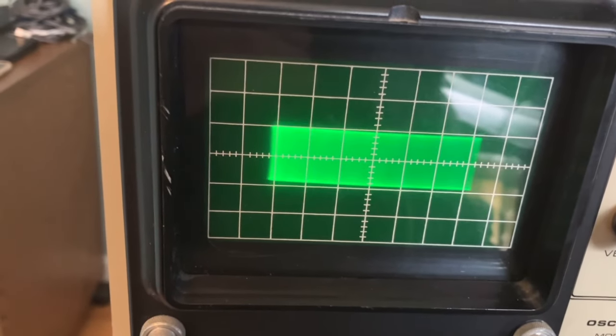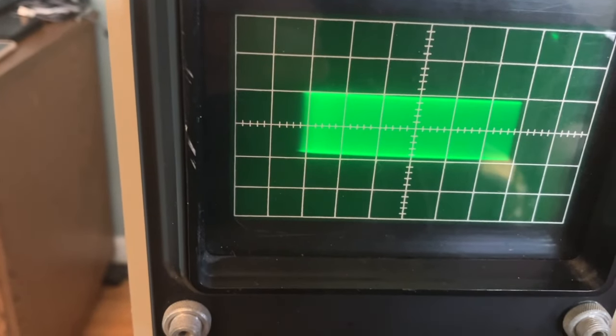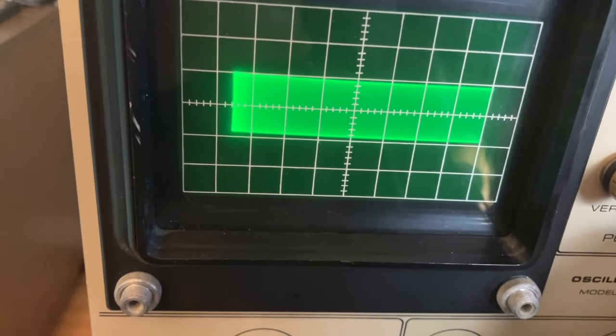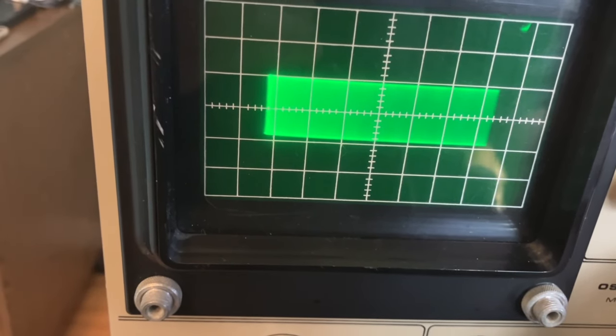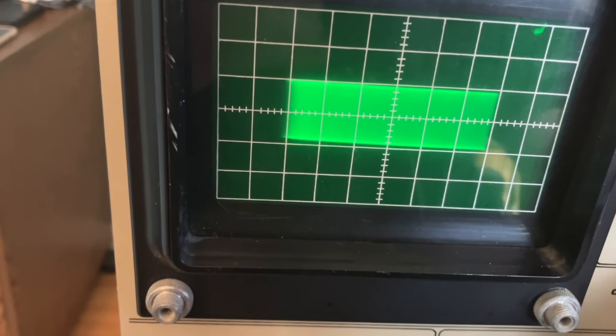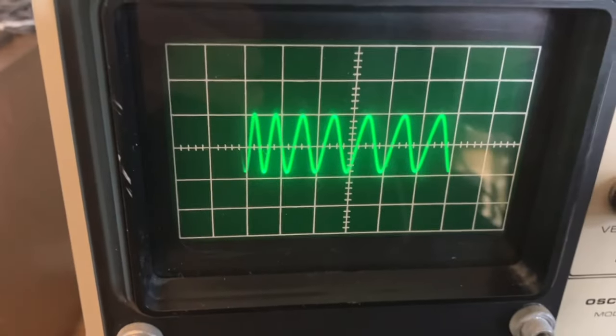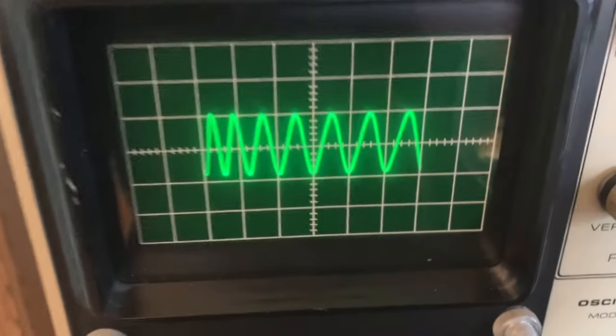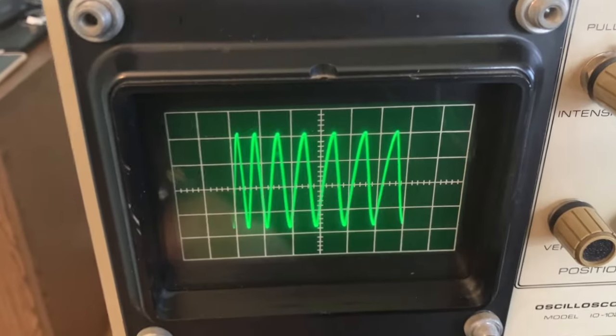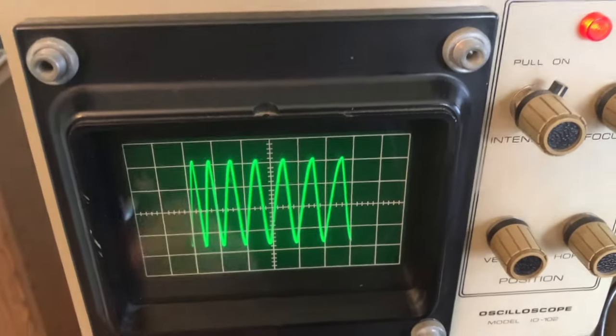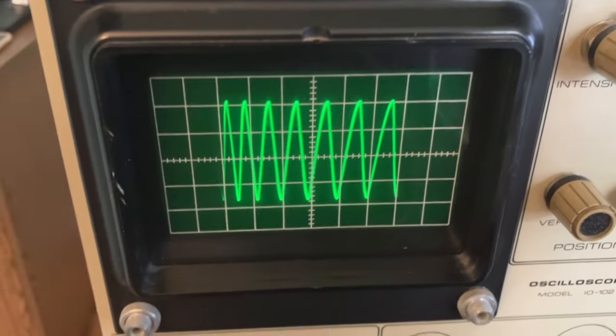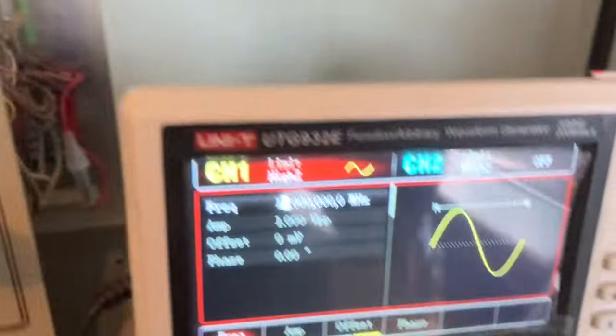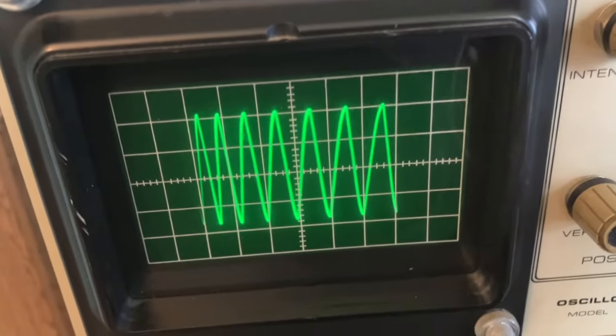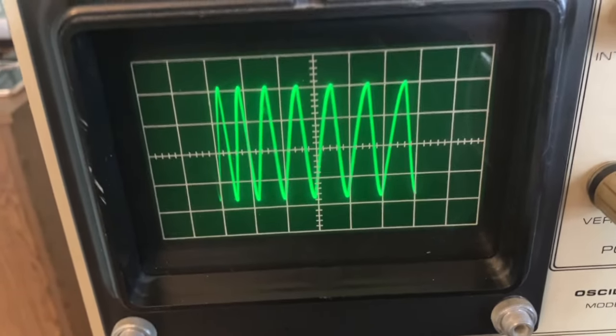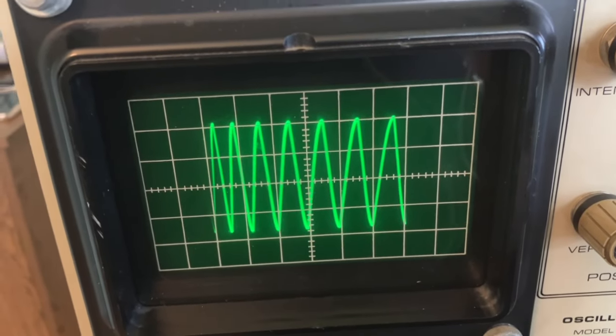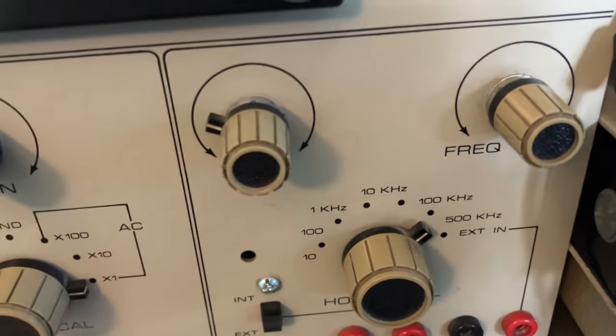6, 7, 8, 9, 10. There's 10 megahertz. Let's see if we can coax it into displaying some number of cycles of this. Oh, there we go. It came and went. So there's 10 megahertz. So now the amplitude is way down below its spec, but it's still displaying something. I suppose I could bump up the vertical sensitivity, turn down the attenuator, turn up the amplitude. This is at its max, and here we go. Oh, by the way, this is a 1 volt peak-to-peak sine wave coming out of the signal generator. So yeah, there's 10 megahertz. So will it go past its 5 megahertz rating? Yes, but not within its response spec. But you can still get stuff out of it, and that's pretty much where it ends for this scope, because it's all the way at the max of its sweep frequency.